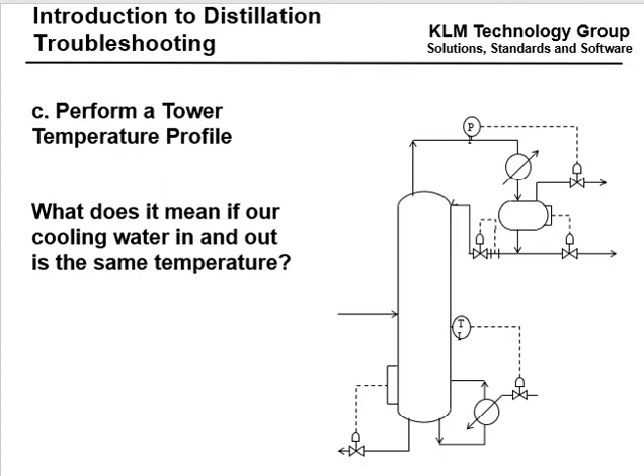What does it mean if your cooling water in and out temperature is the same? It could mean your overhead condenser is fouled. If it's clean service, it may mean you don't have the right amount of flow through the overhead condenser. If you have low pressure and the cooling water temperatures in and out are similar, check the reflux flow meter and reflux control valve to determine if you have the right amount of reflux going into the column.